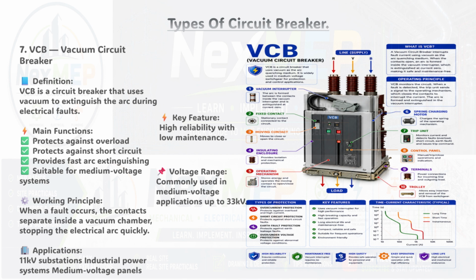Now let's talk about VCB, the vacuum circuit breaker. Moving up from low voltage, VCB operates in the medium voltage range. The arc quenching medium here is vacuum, and vacuum is an excellent arc extinguisher because there are no particles to sustain the arc. When a fault is detected, the contacts inside the vacuum interrupter separate, the arc forms, and it gets extinguished at current 0, almost instantly. VCBs are your go-to for 11 kV substations, medium voltage switchgear, and industrial power systems. The voltage range is typically up to 33 kV.